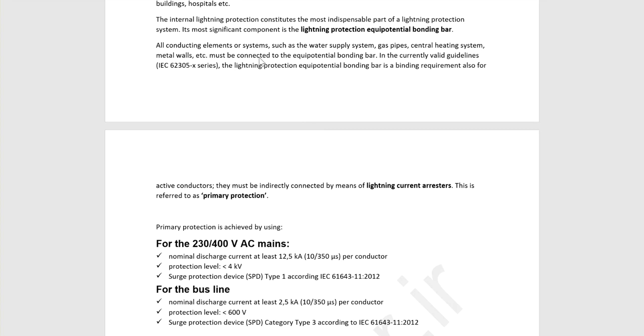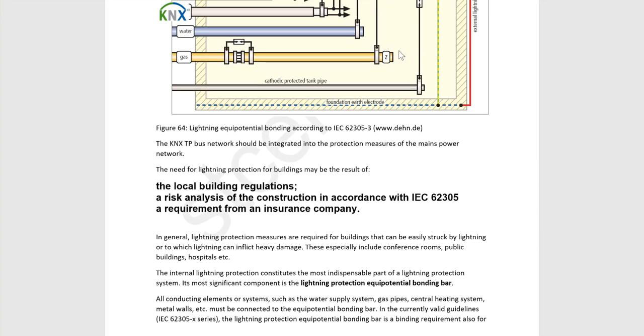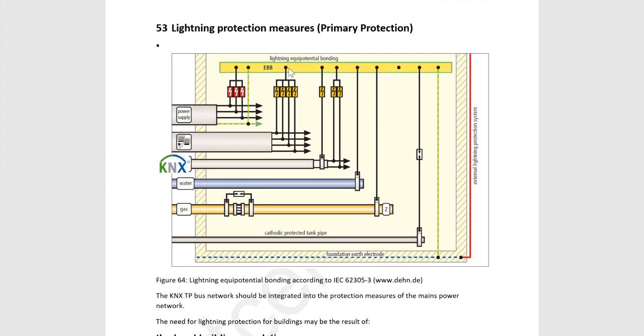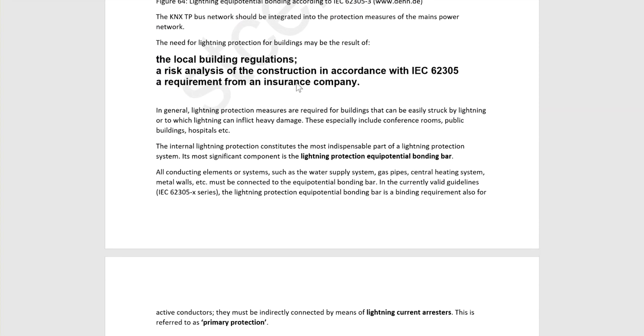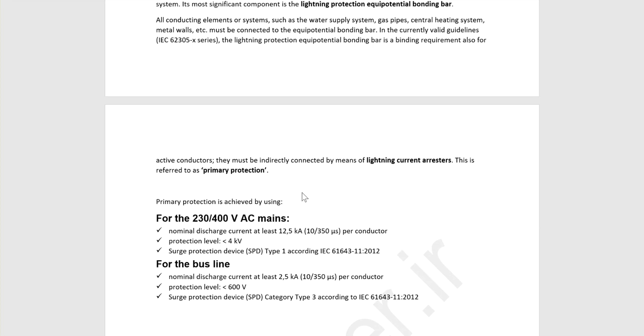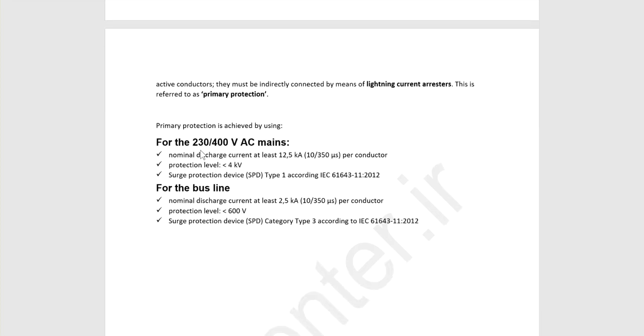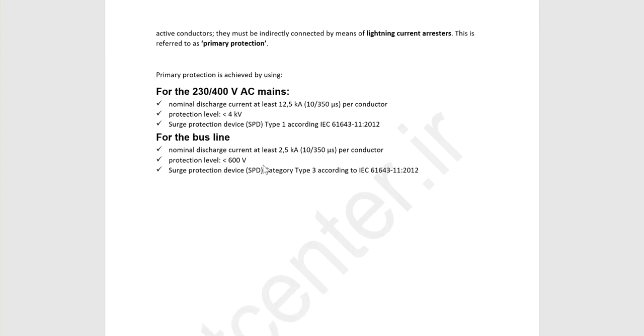All conducting elements or systems, such as the water supply system and gas pipes, should all be connected to the equipotential bonding bar. They must be connected to the equipotential bonding bar. In the currently valid guidelines, the lightning protection equipotential bonding bar is a binding requirement also for active conductors. They must be indirectly connected by means of lightning current arresters. This is referred to as primary protection. Remember that if you want to connect the KNX lightning protection as a secondary protection, you should always first have the primary protection. Okay, so you should have the primary protection, then you can use the KNX protection as a second one. Primary protection is achieved by using devices for 230 volt and 400 volt voltage. You can always follow this as a standard.